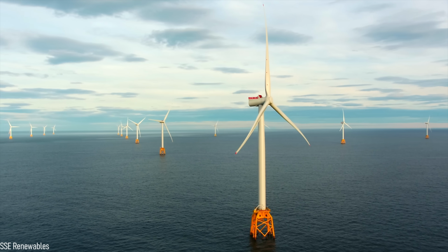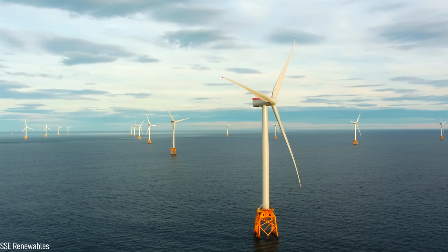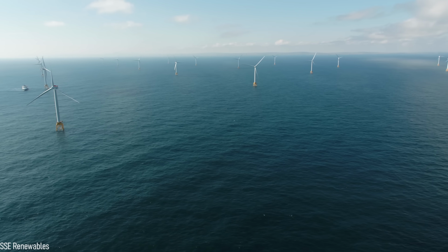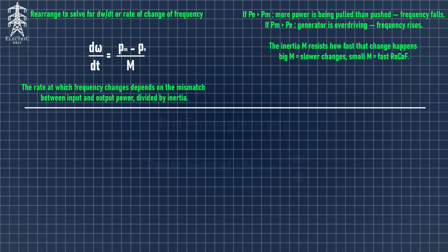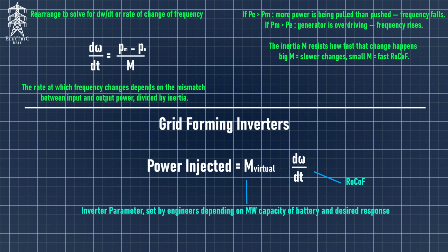Well, wind turbines and solar farms normally need power from the grid to operate the control systems and inverters. Without a stable grid signal, they can't synchronise and connect properly. However, modern offshore wind farms, like Dogger Bank, are starting to use advanced grid forming technology. Solar farms, on the other hand, almost always require an external grid signal to operate. Very few solar sites today have grid forming capability, although that's slowly changing with new inverter designs.